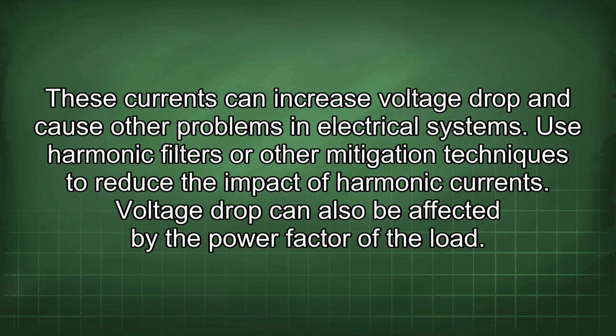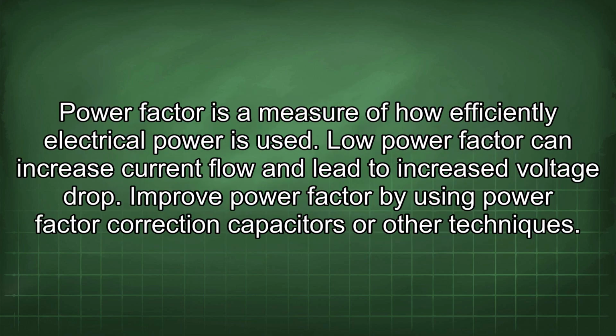Voltage drop can also be affected by the power factor of the load. Power factor is a measure of how efficiently electrical power is used. Low power factor can increase current flow and lead to increased voltage drop. Improve power factor by using power factor correction capacitors or other techniques.